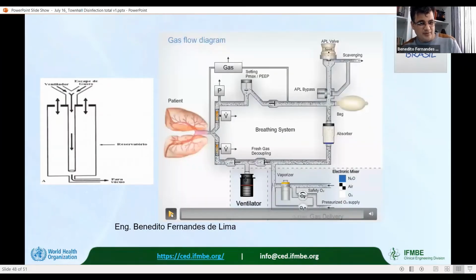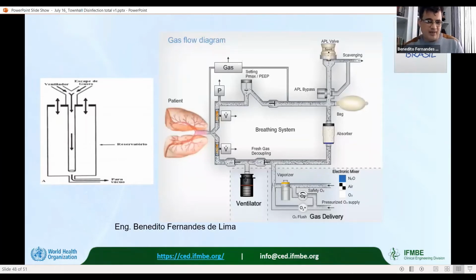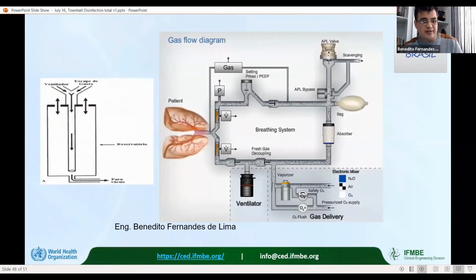Regarding anesthesia equipment, we needed to relocate a lot of equipment previously used with outpatients, and now they are used only in patients with coronavirus. So we had to choose anesthesia equipment with the least difficult level of reprocessing. One of the great difficulties was the process of disassembling the anesthesia subsystem and sending it for sterilization and then reassembling it, considering that the assembly process is carried out by the clinical engineer team. The devices are subject to high temperature and pressure, so it is necessary to double-check the integrity of the equipment after reassembling it. Next slide, please.